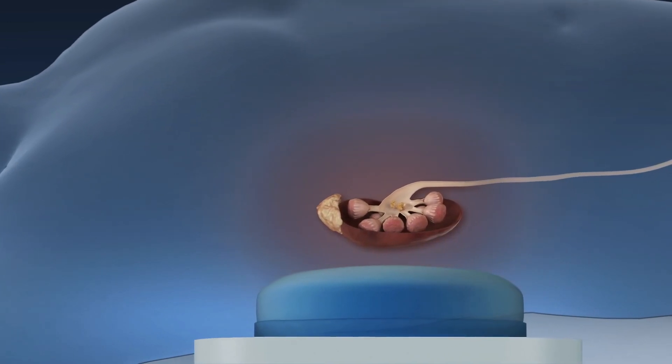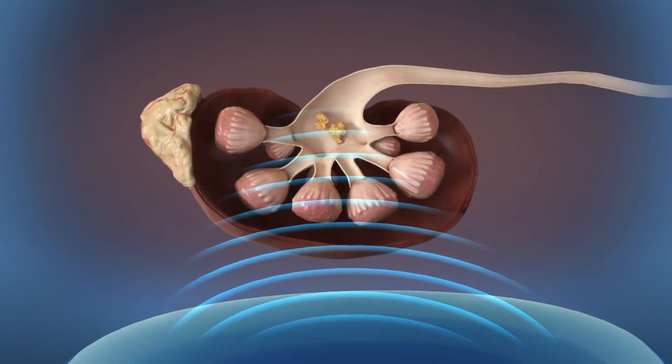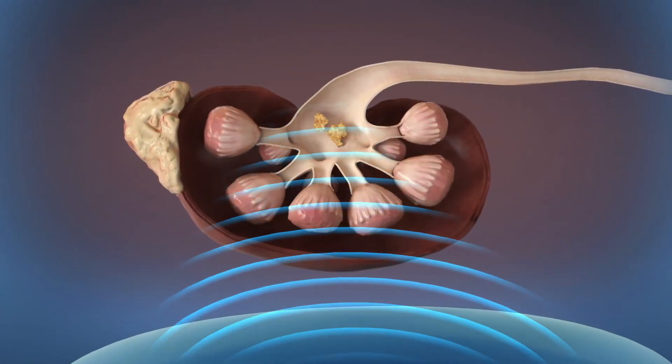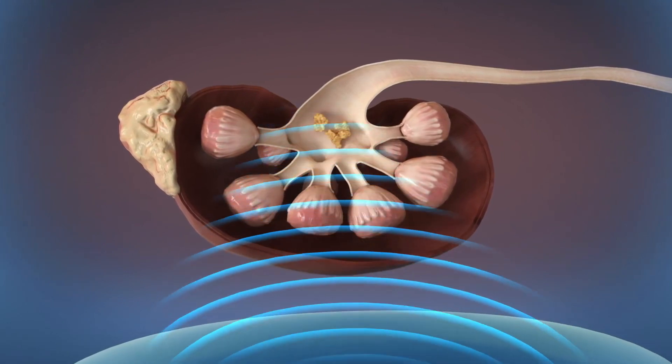The first method is electrohydraulic. The original method of shockwave generation used in the Dornier HM3 was electrohydraulic, meaning the shockwave is produced by spark gap technology. In an electrohydraulic generator, a high voltage electrical current passes through a spark gap electrode located within a water-filled container.